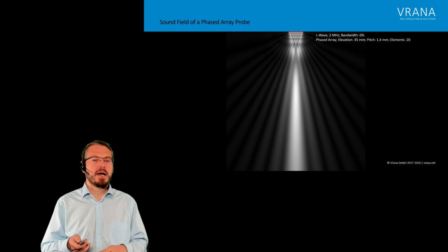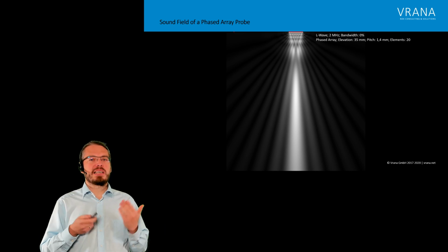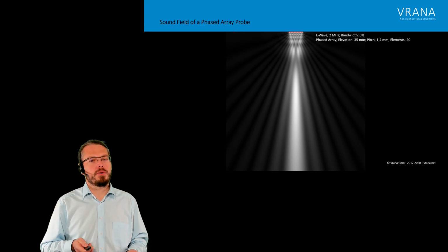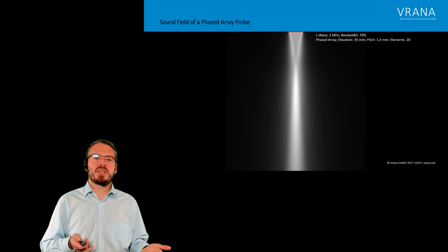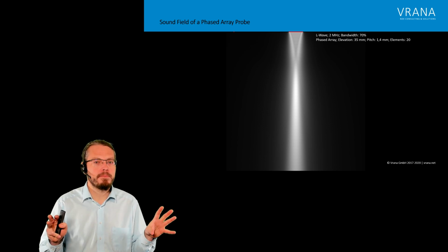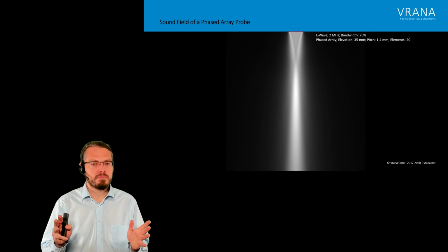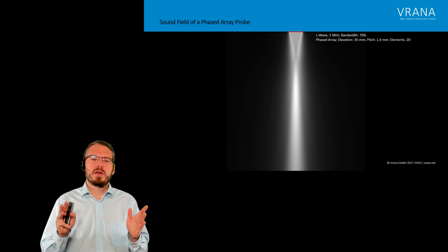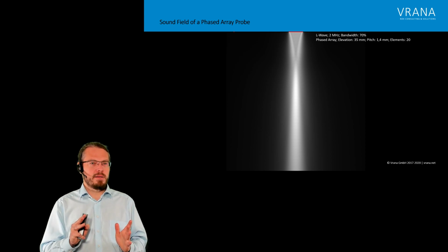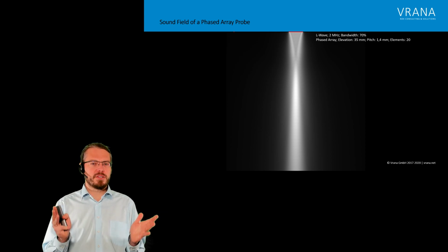But this probe actually has a bandwidth of 70%. So let's take that into account. And you see, again, all those interference patterns are gone, and all those side lobes are gone or very, very minimal. So you will not see them during your inspection.